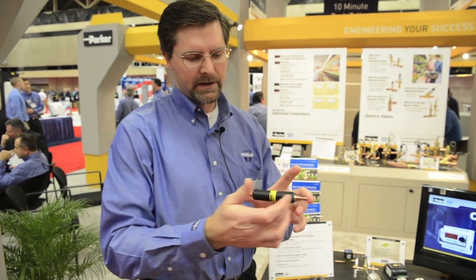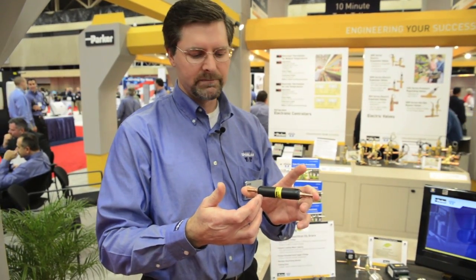I'm introducing the Parker Sporlan new CO series of filter dryer components, which is specifically designed for bottle coolers. The construction is a spun copper filter dryer where we put an aluminum sleeve on the outside of it. We did that to increase the pressure rating.